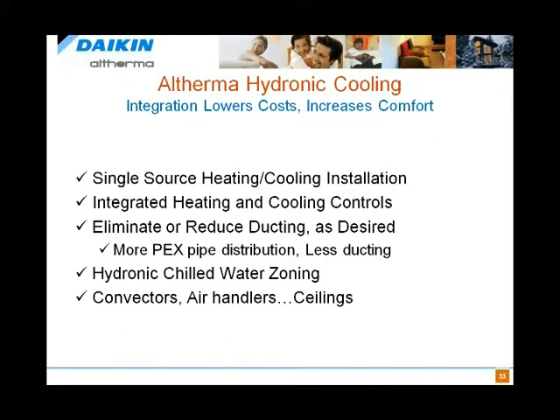So now that we're doing hydronic cooling, we can help in reducing ducting as desired with air handlers and different convector designs. We can use more PEX pipe distribution going out to these terminal units and less ducting. And we have the opportunity to be doing hydronic chilled water zoning, which is much more flexible and can be more cost effective than doing air style zoning with cooling systems. So that whole business of total redundancy between having hydronic heating and an entirely separate cooling system no longer applies when you're dealing with this type of system.